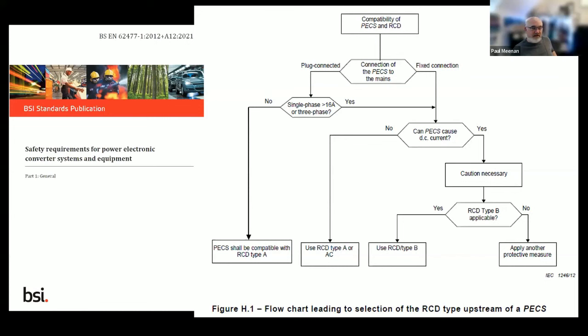And if it does, is type A enough? Have we done enough? One of the interesting pieces in this was that when you apply another protective measure, one of the recommendations was double insulation. So double insulation plus your type B. That way, if your RCD didn't work, you still have the additional measure of double insulation. So there's some fascinating knowledge in the standards that helps you consider your RCD protection more.